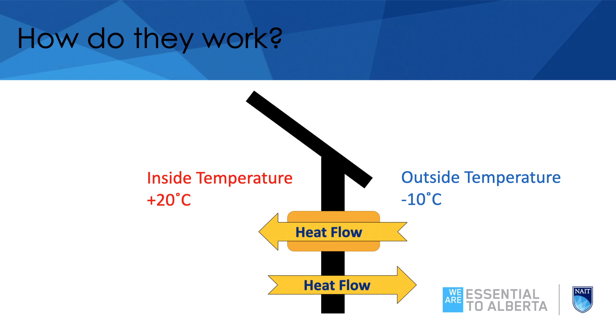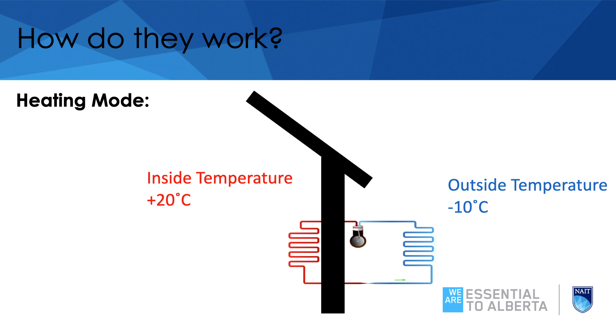At minus 10 there's not much heat in the air, you would think, but there's about 85% of the heat that we have at plus 20. We have two coils, one on the inside and one on the outside. Inside those coils there's a refrigerant that flows in circles, powered by a compressor. One side is cold, the other side is hot. As long as the cold coil is colder than the outside temperature — let's say minus 50 degrees — heat will flow from the minus 10 air into the refrigerant. It goes through the compressor where it gets upgraded to a different temperature. As long as the hot side is hotter than the inside, the heat will go into the building.